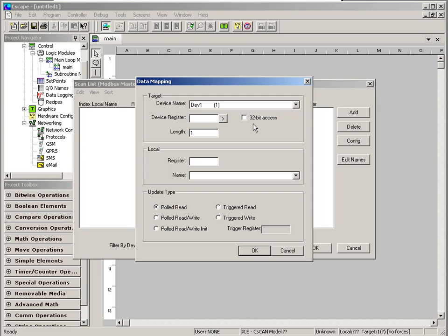So in some devices, let's say the speed feedback is in parameter 0303, we would use an address something like this. And this only applies to one type of device. We go 40303. Many devices, especially drives, adopt the idea where you take the parameter group and the parameter number and put a 4 in front of it. Again, it's going to vary from device to device. Length is 1. This 4 indicates it's a 16-bit register, and we're going to take one of them.